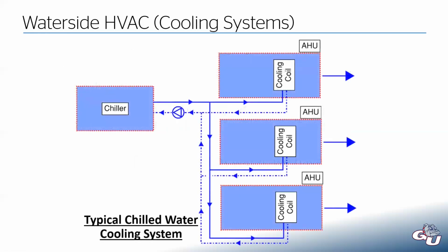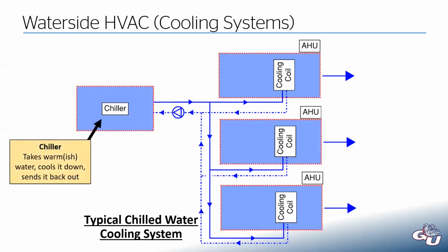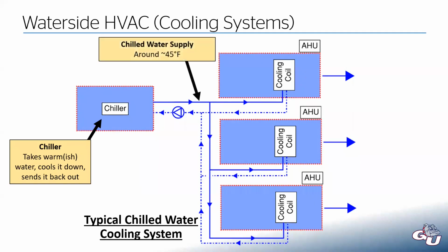Here's a basic chilled water cooling system. And at a glance, you're probably going to notice that, hey, this looks very, very similar to a hot water system. In this case, we have a chiller, which is going to take warm-ish water and cool it down. It will chill it and then send it back out into the system. We have our chilled water supply, which is going to be around 45 degrees. So that is what is leaving the chiller. That's what we are cooling down our water to.